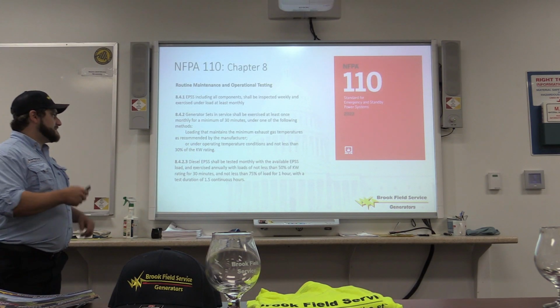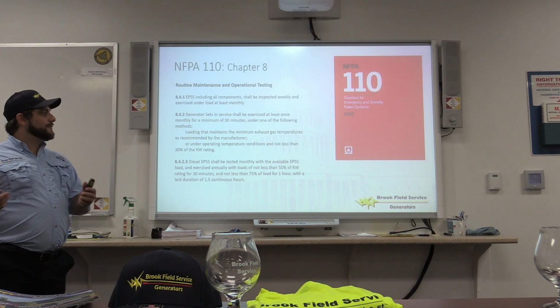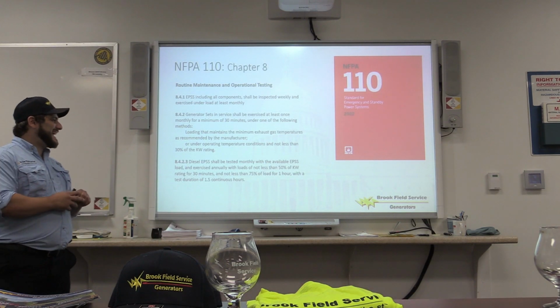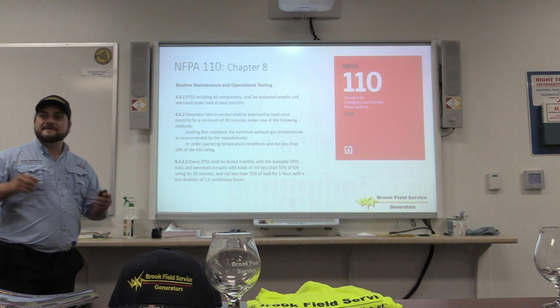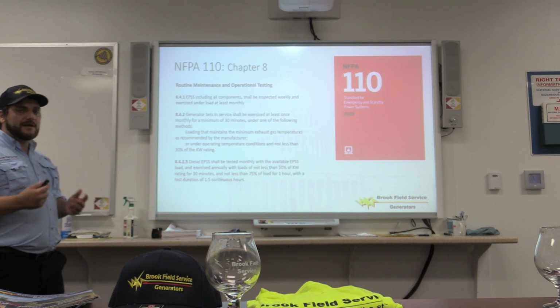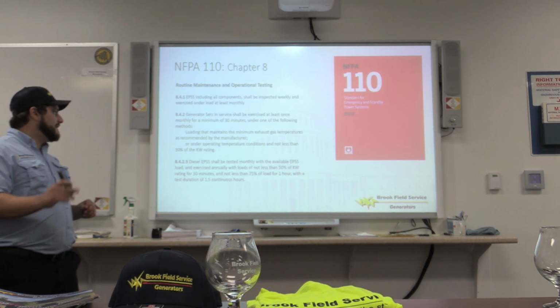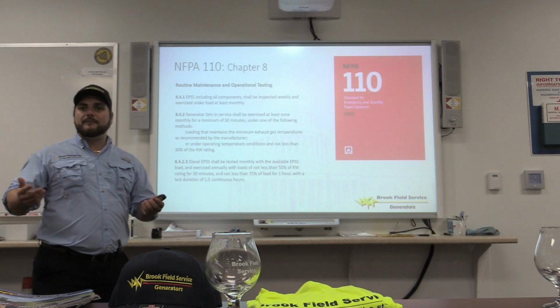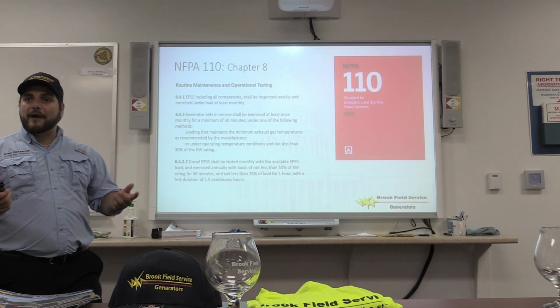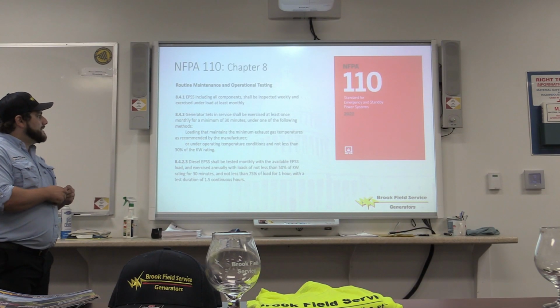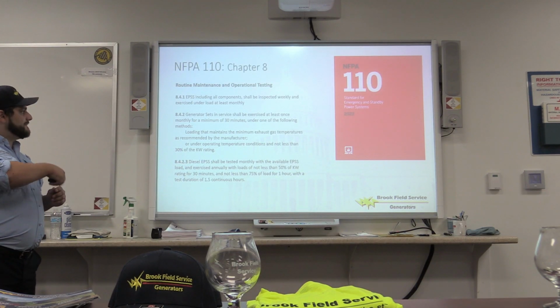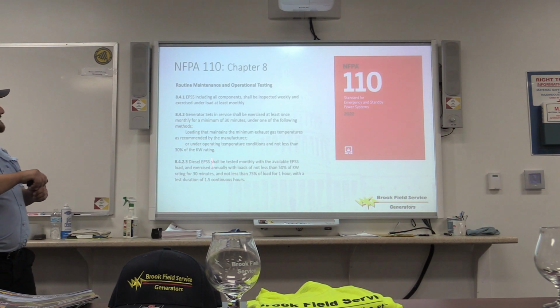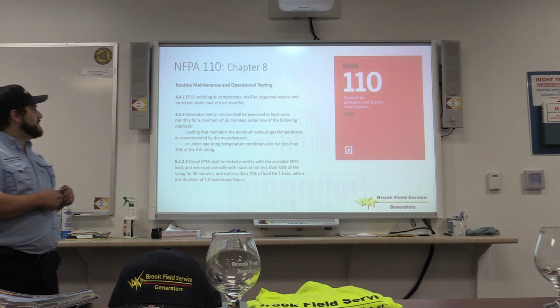Diesel EPSSs shall be tested monthly with the available EPSS load and exercised annually with loads of not less than 50% of kilowatt rating for 30 minutes and not less than 75% for 1 hour, with a continuous run time or test time of an hour and a half. And again, we'll get into more of the importance of why the testing is so important, especially with the load ratings for the diesel EPSSs.